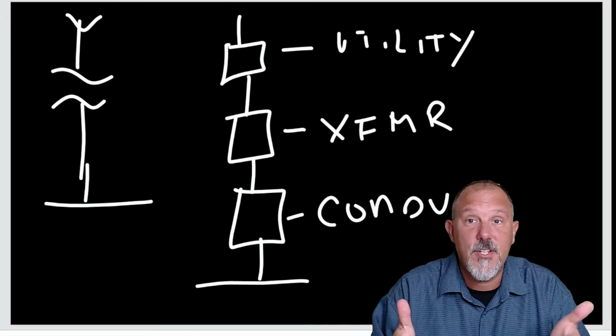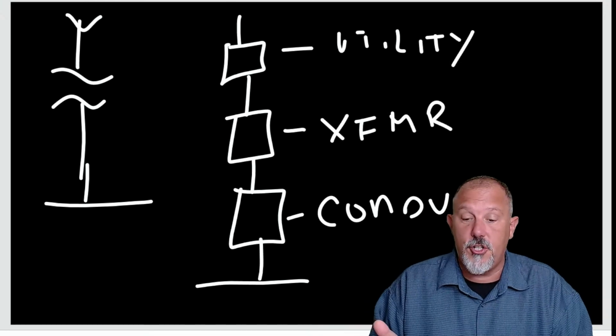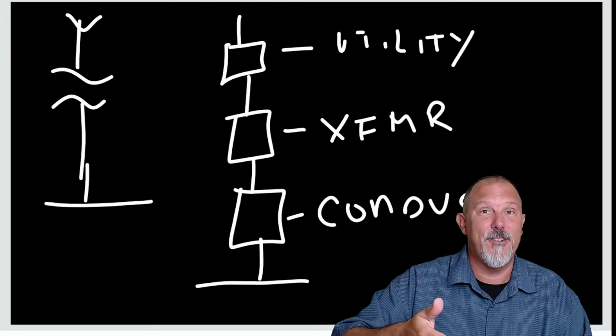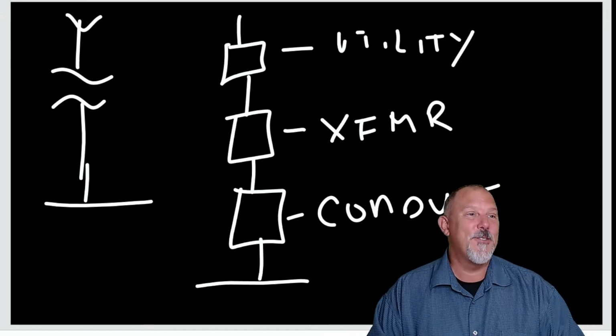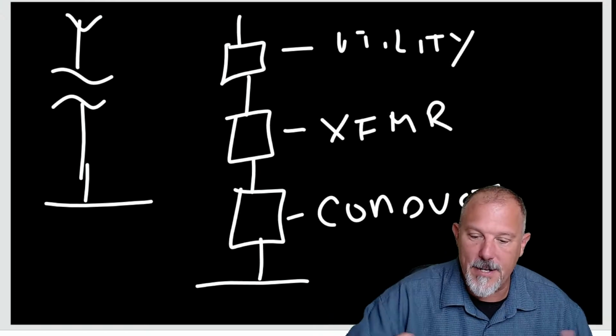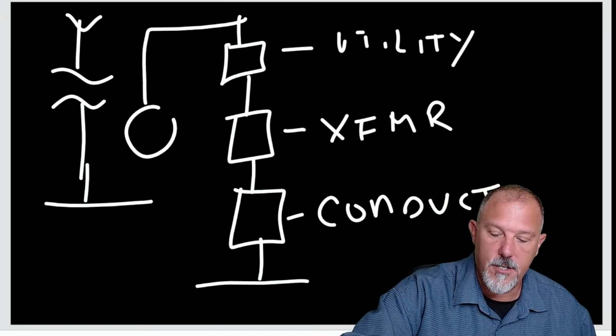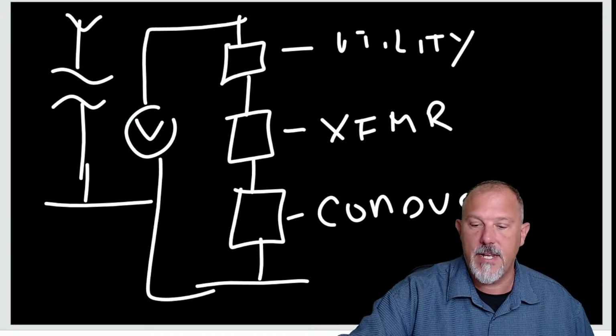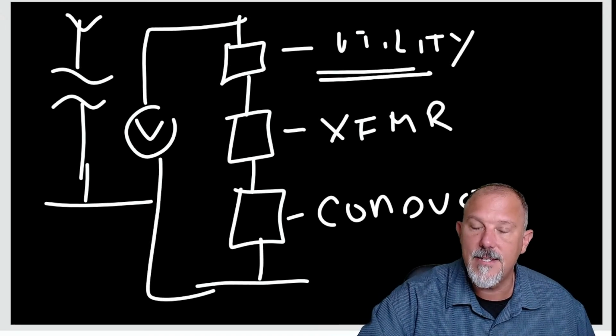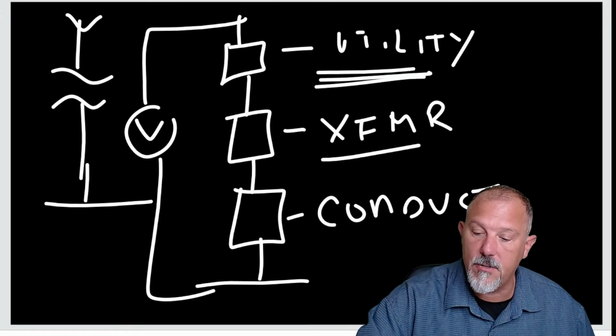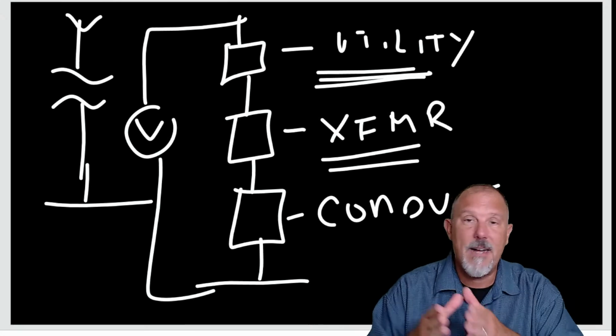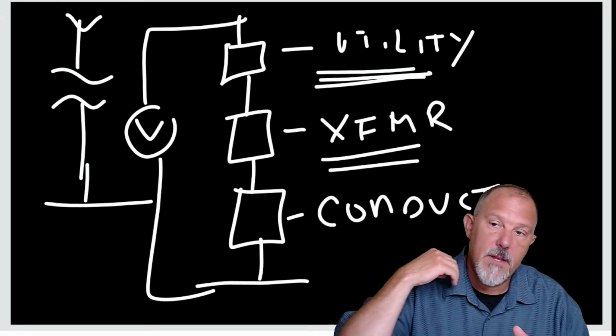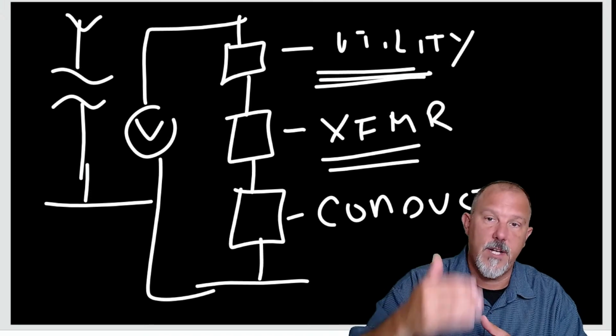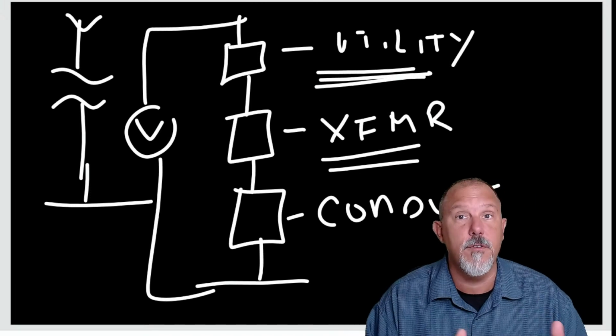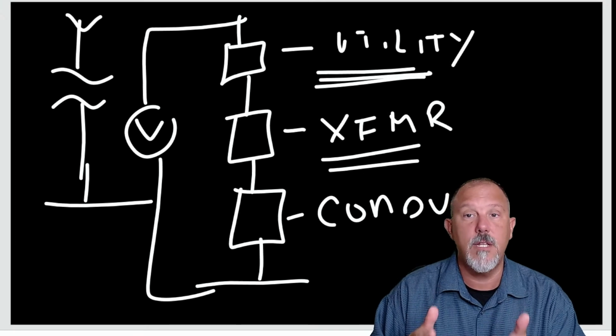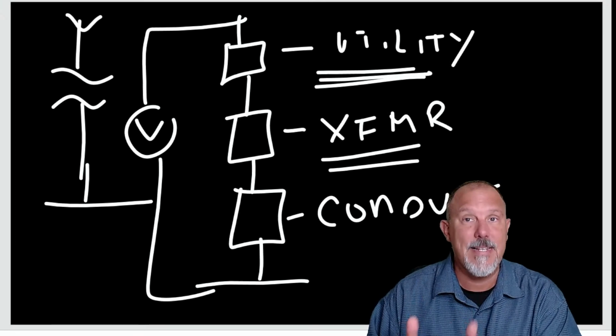And what this all comes down to is your basic short circuit calculation, your ohms, your Kirchhoff's laws, your Ohm's law of V is equal to IR, right? So how do I do this? I just draw a voltage, and these are all of my conductors. This utility impedance is really small as compared to the transformer impedance. So it's about the impedance of the transformer. That large impedance of the transformer in this circuit is what governs the available fault current. Regardless of that utility, it's so small, it's almost insignificant.